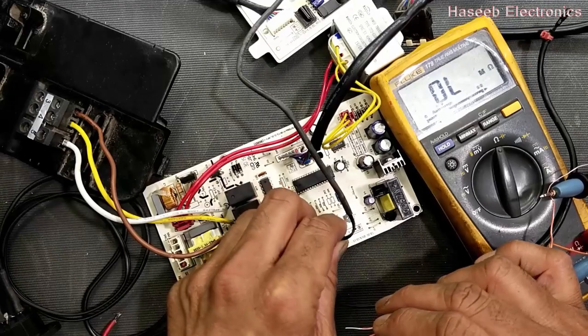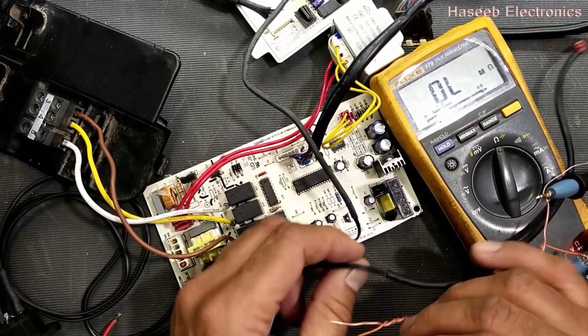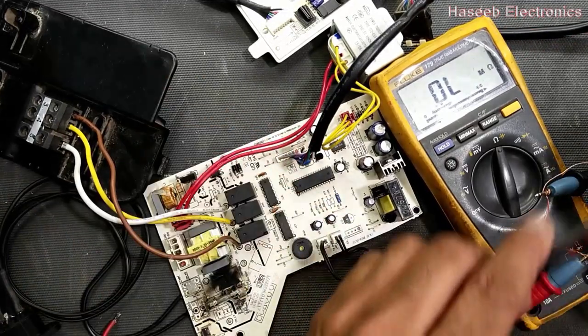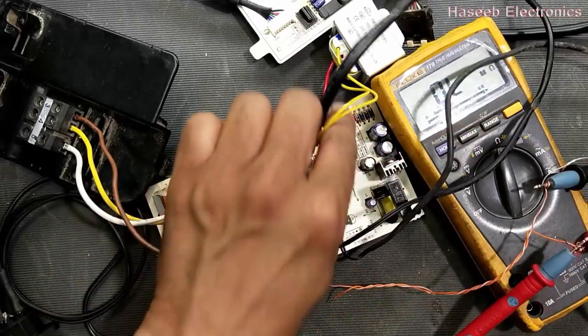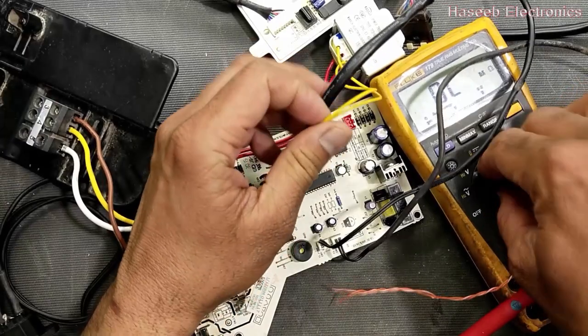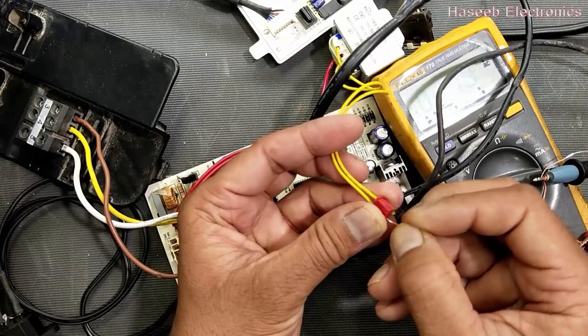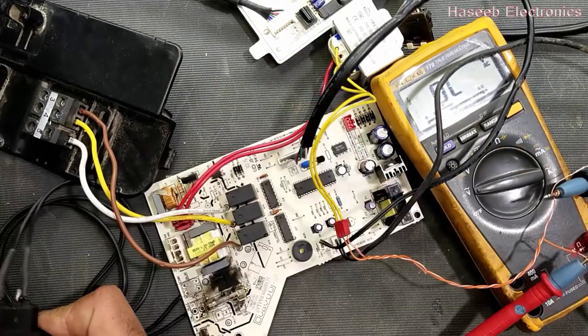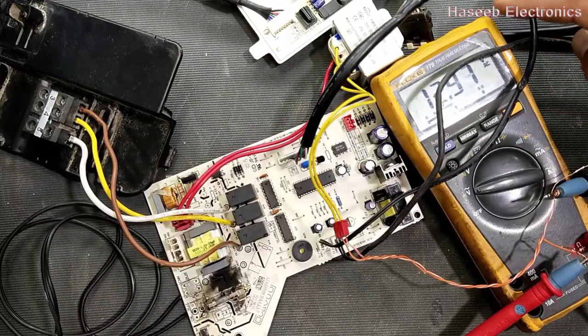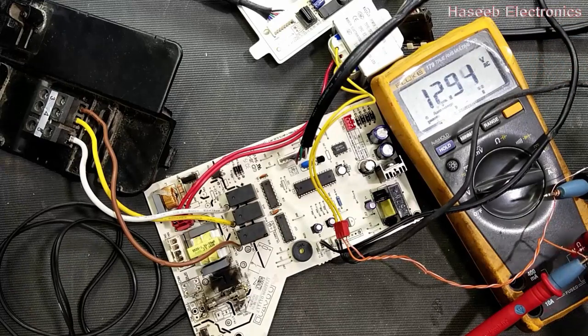We tested both temperature sensors, the room temperature sensor and the pipe temperature sensor. So these are good. And we can also verify the output of this transformer. Set multimeter to AC voltage. Connect to both outer leads. Connect power. So it is giving 12.96 volts.